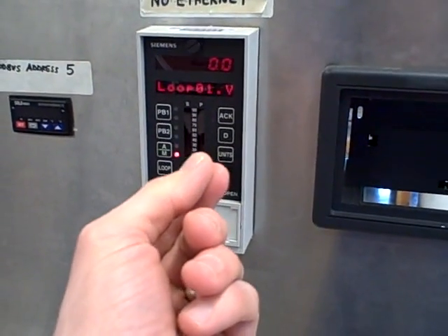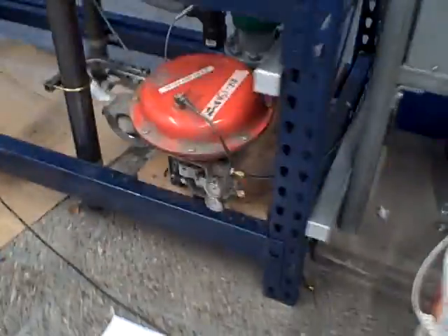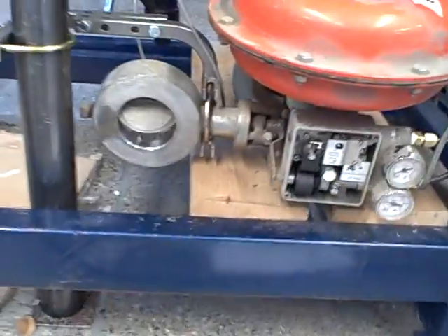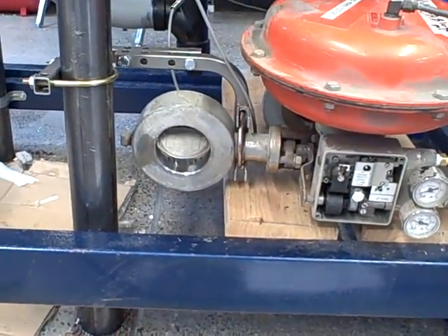So right now it's 0% — one valve should be wide open, the other one should be fully shut. Looking over here, a wide-open valve is this one right here. It's a rotary valve, a little butterfly or disc valve right there — it's wide open. The valve that's all the way shut is a Fisher E-body globe valve over here, and this is currently all the way shut.